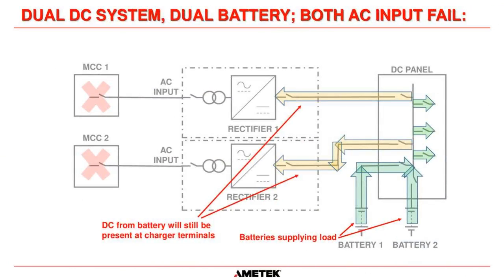Now, if we had a whole plant outage, if we'd lost complete power to the plant, so MCC1 is out, MCC2 is out, then basically both batteries in parallel will feed power to the load circuits. Obviously, there will be voltage going back to the terminals inside charger 1 and charger 2, so be careful about that. But when both systems lose AC power, that's when the batteries take over feeding the load.